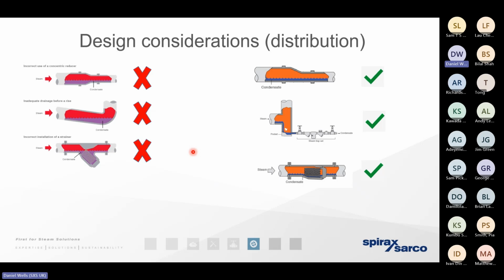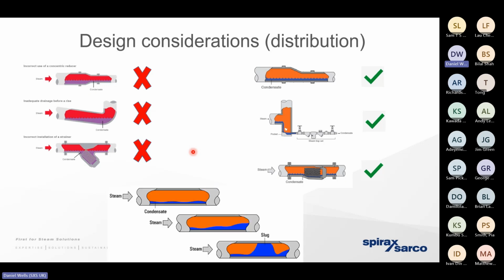We're going to have a biphase in the pipework. We're going to have the steam as a gas, with all of that useful energy in it, that wants to move at a very fast velocity. And we're going to have the condensate as a liquid, as a result of that heat loss, that we need to drain away. So we need to separate the two. We need to apply best practice to get that condensate away as quickly as we can, so we don't have problems with erosion, corrosion, and especially water hammer.